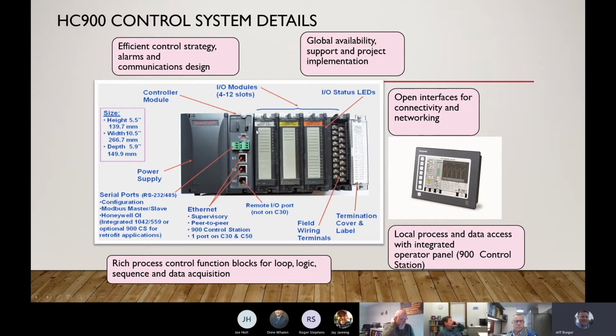As we move over to the right-hand side, you now have your I/O modules. You can have a 4, 8, or 12 slot rack. Each one of the slots starts with the very first I/O card, so that would be slot number 1. These boards can come in many different flavors. You can have analog out, analog in, which are both universal. You can have digital in, digital out, dry contact. So there's a lot of different versions or variations of those I/O modules that you can have in the rack.